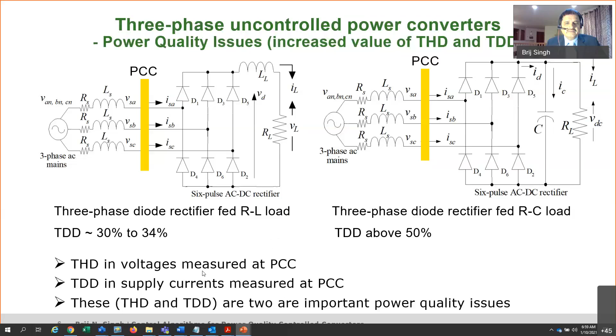As your demand, like load demand, which is reflected by current, is varying, then you would have variable TDD, right? And these are two power quality issues, and there are numerous others, like voltage flicker, voltage fluctuation, and then brownout, blackout, single phasing, and voltage unbalance, and all those kinds of stuff. Voltage and current inrush are additional issues, but THD and TDD are usually the most important power quality issues that a load can introduce.